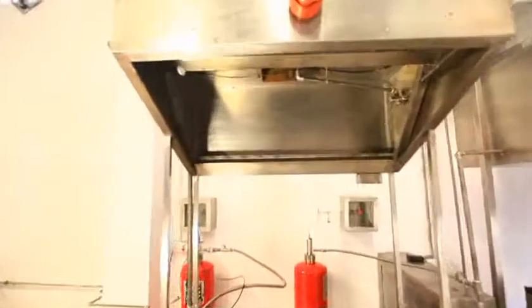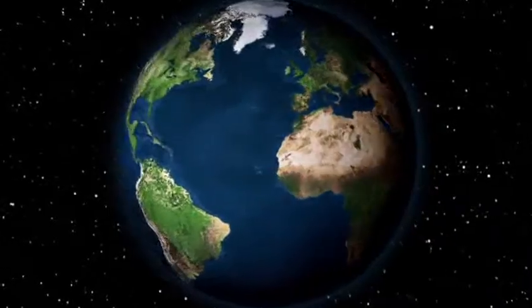Water may be fire's most potent enemy, with its massive cooling power of 2.6 MW per liter per second. But you need a lot of water to put out a fire effectively. Often there's post-fire collateral damage too, because water damages furniture, valuable objects, and electronics like computers. And then there's the added danger of electrocution when trying to battle fires involving electronic devices. The need for today, then, is cutting-edge technology that changes water's natural form so that water can fight all kinds of fire without causing any collateral damage to the premises or the earth. We call that firefighting technology water mist.